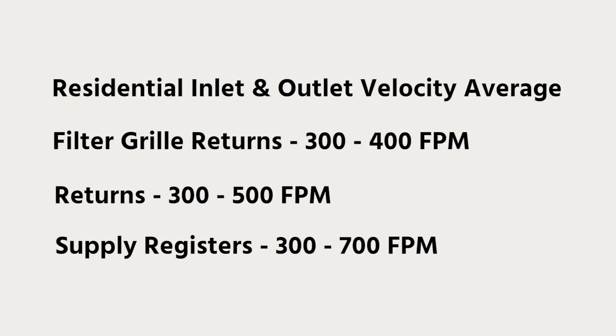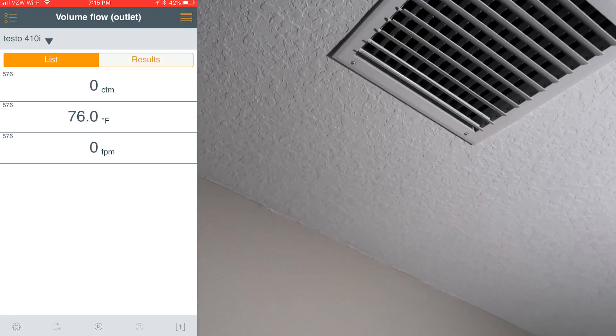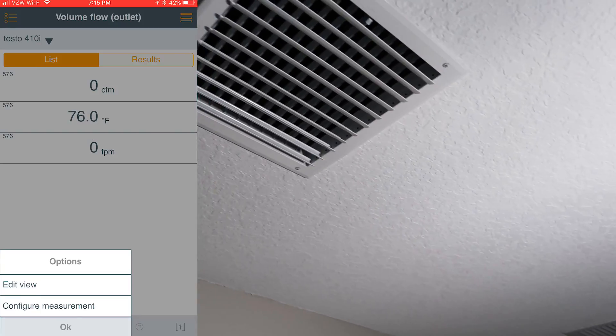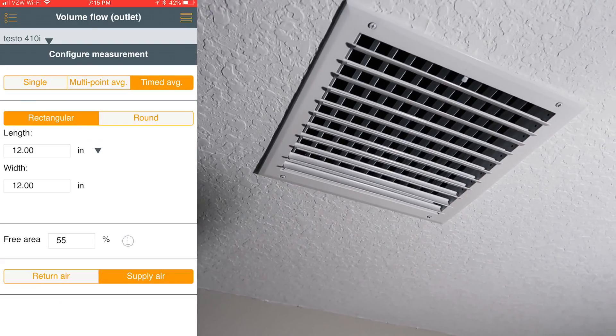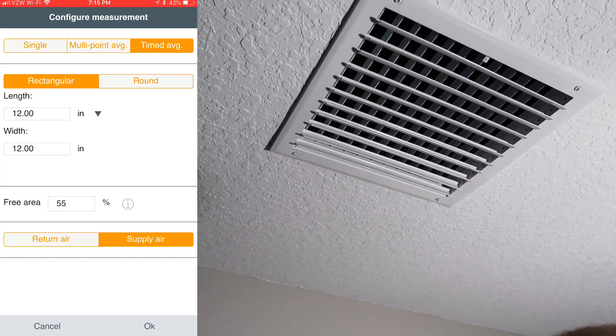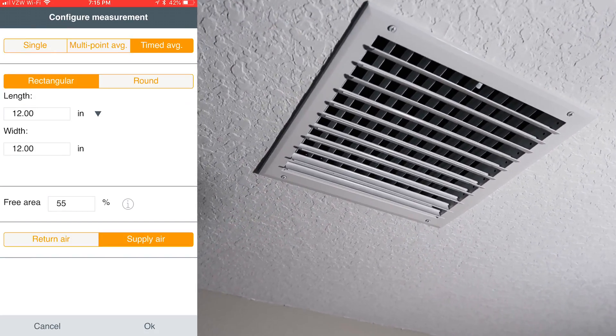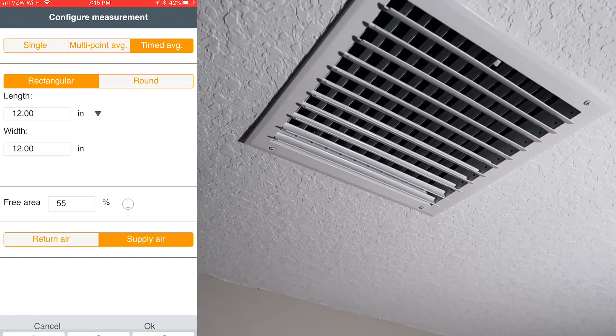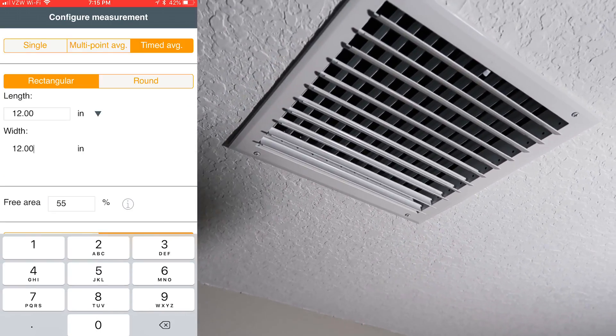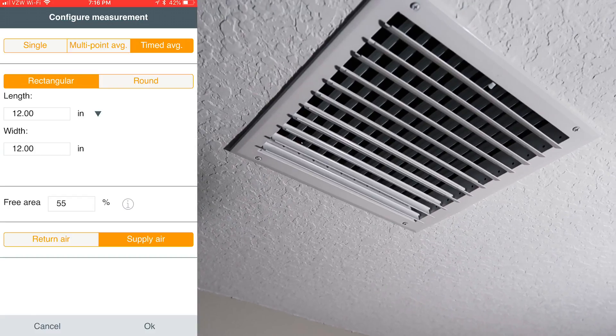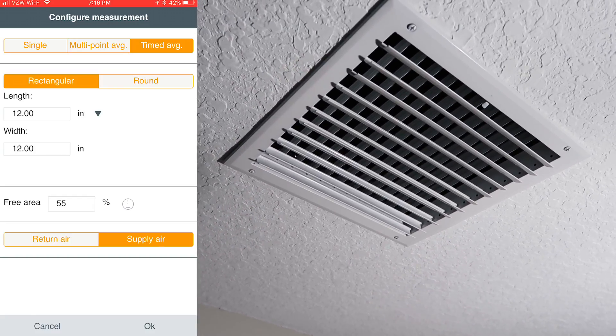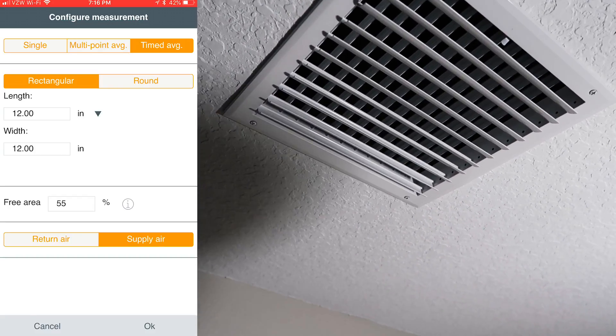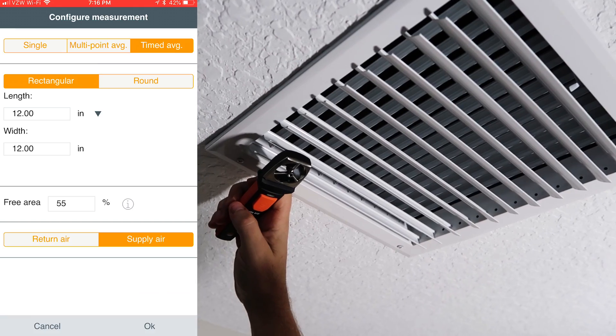I've intentionally set really low velocities on this for the purpose of having low air noise. I'm going to be doing a timed average traverse. You can see I've got it already set in a 12 inch by 12 inch, 55% free area — that is off the specs for this actual vent. You have to look carefully at the specifications for the vents in order to find that. But in general, you can use this to average the velocity and paint the entire vent.